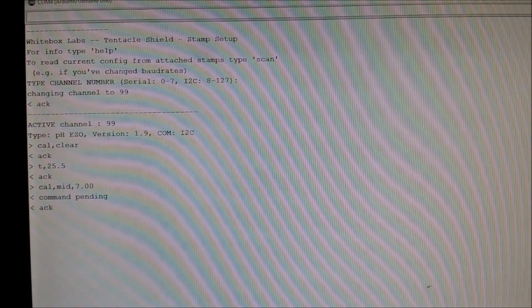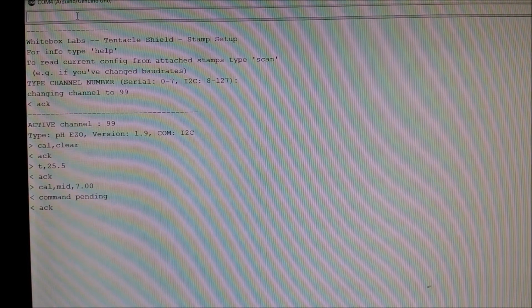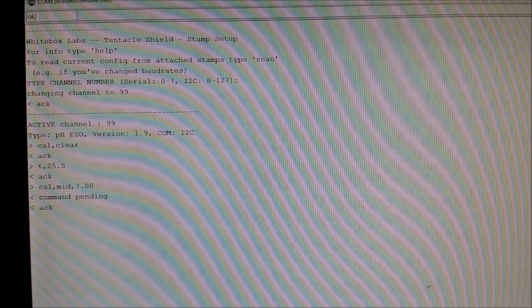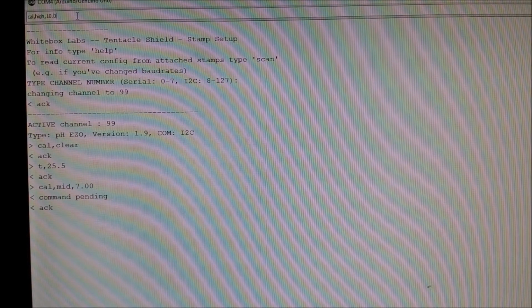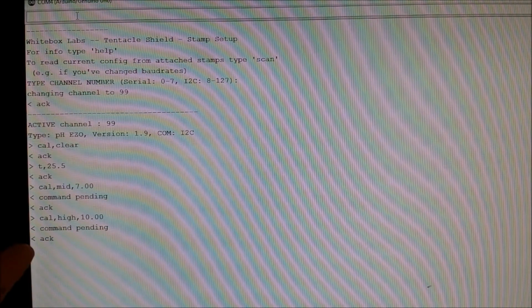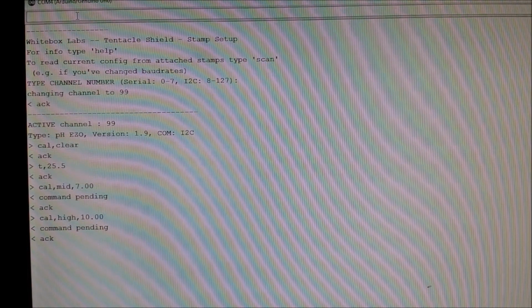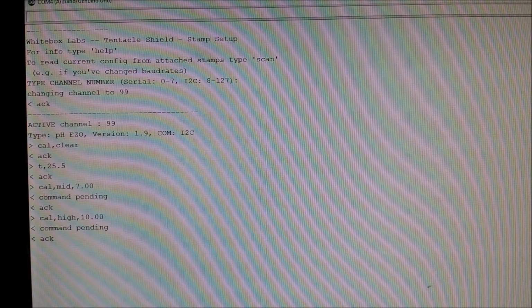Okay, so it's been about 5 minutes since I put the probe in pH 10. So now I'm going to calibrate it for the high. So it's cal, comma, high, comma, 10.00, and then enter. And you see command pending, and then acknowledge. And that's it for the calibration. Now I am ready to actually get the pH.